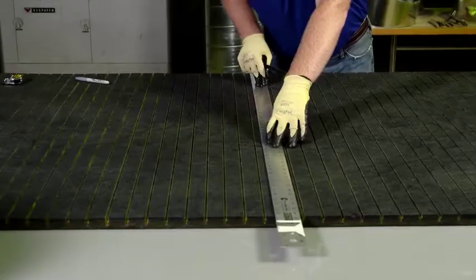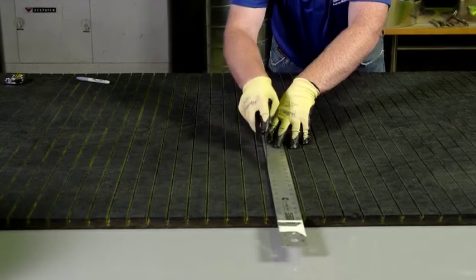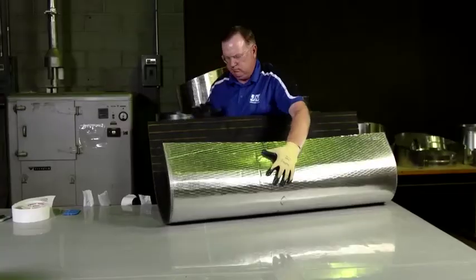First, calculate the circumference of the pipe by multiplying pi times the diameter. Then measure and cut the length of the Spiracoustic Plus to three quarters of an inch less than the circumference.